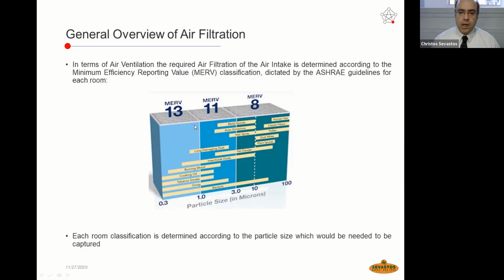And this is an exercise that we must make in our room, not only the oven room, in every kind of room where we're going to need air treatment as well. This is an exercise that we need to define in order to define which kind of air filtration we need to have in our room. Do we need to isolate mold spores? Do we need to isolate burning wood, cooking oil, tobacco smoke, smog? Do we need to isolate bacteria? And which kind of particle size of bacteria do we need to isolate? From 10 microns to 3 microns to 1 micron down to 0.3 microns. So each room classification is determined according to the particle size which would be needed to be captured. This is an exercise that we must make internally, with which we can define the proper air filtration system.